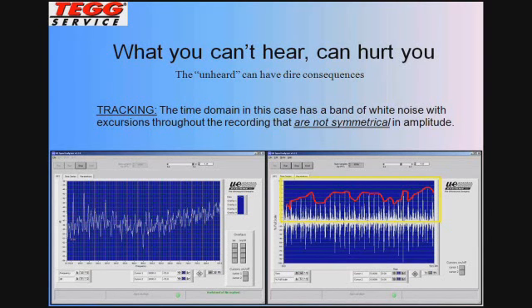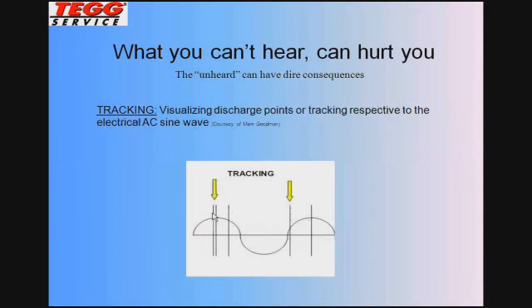Another thing I have found is the more tightly compact that these excursions become, in other words, a higher rate of frequency that the discharges are occurring, the more severe the tracking is becoming. So that's one of the key things I focus in on here with tracking, is looking for those excursions that are not symmetrical in the amplitude and become more tightly compact, suggesting that the discharges are occurring at a higher rate or a faster rate. On the sine wave, again, similar to the arcing, you get the asymmetrical patterns there and the lack of consistency in the timing, because the discharges could occur at any point on the sine wave.